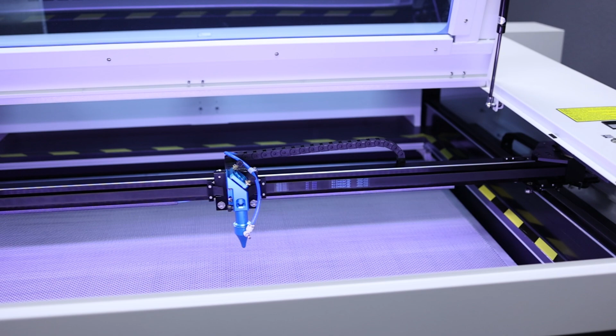In some regions the tube is glass, and you have cold water coming in. At certain temperatures you want your tube controlled by either a chiller or a heating system. This preheats the water going through the tube, so it isn't exposed to cracking or prolonged misuse. That's one of the things we've offered because that's something our customers gravitated toward, so we offer that as well.